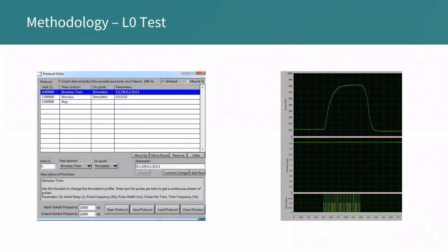Once the mouse is ready, the first experiment to be done is to adjust the muscle to the optimum length, which we call the L0 test. For this test, the sciatic nerve is stimulated with a single electrical pulse just to produce a twitch response. Then the muscle length is adjusted to longer or shorter lengths depending on the curve obtained. You can see an example of this test on the right. The baseline should be at the same level before and after the stimulation. The optimal muscle length L0 is achieved when the twitch force is maximal.